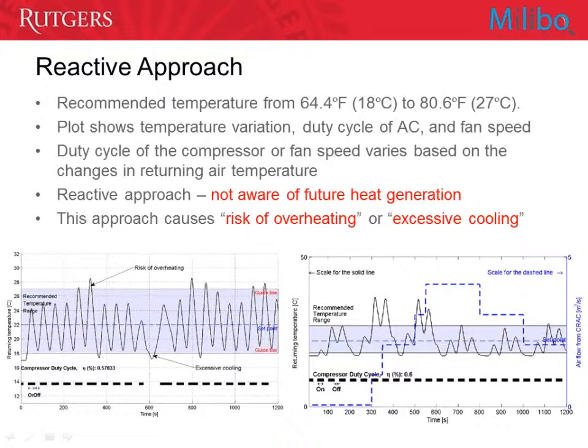On the left-hand side, we fixed the fan speed and changed the duty cycle of the air conditioning system. On the right-hand side, we changed the airflow but fixed the compressor duty cycle. We clearly see a risk of overheating and excessive cooling, which wastes energy or puts servers at dangerous temperatures.